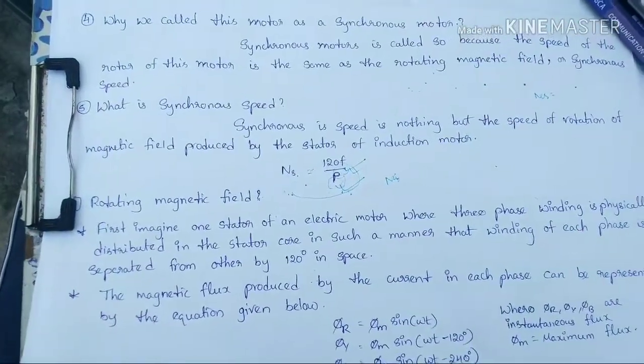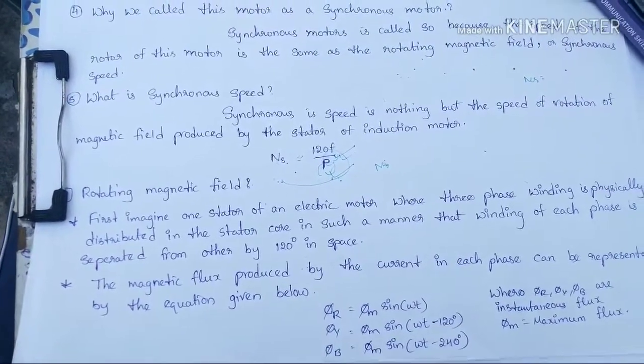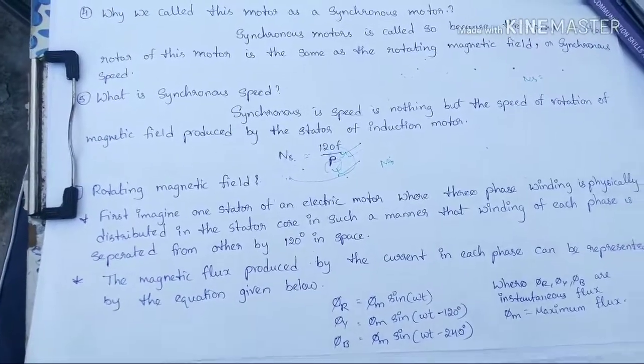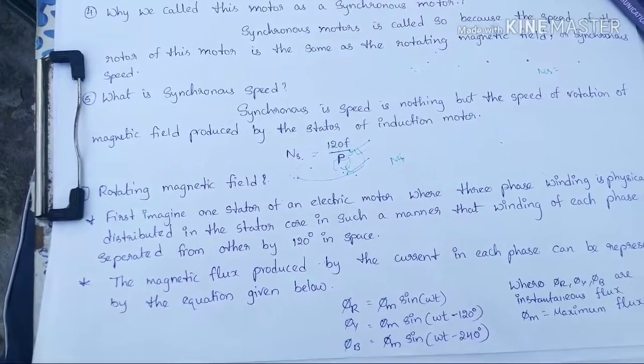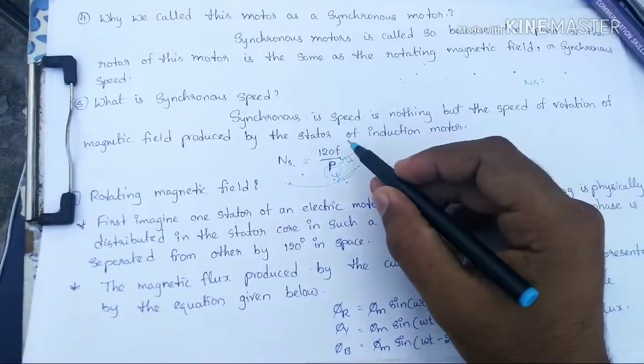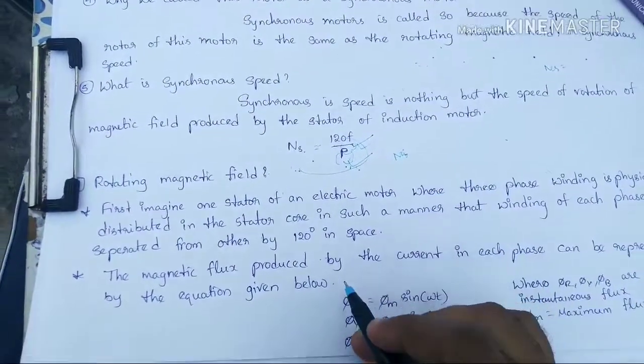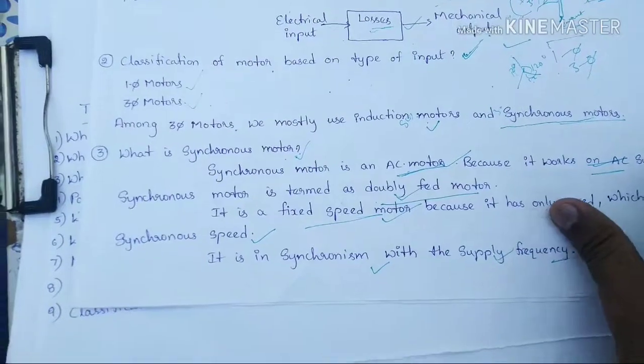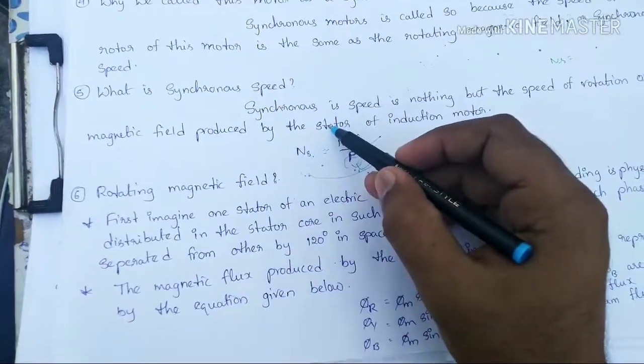The synchronous speed is directly proportional to the supply frequency — if frequency increases, speed increases; if frequency decreases, speed decreases. The synchronous speed is inversely proportional to the number of poles — if poles increase, speed decreases. The number of poles in a given motor is fixed and constant.